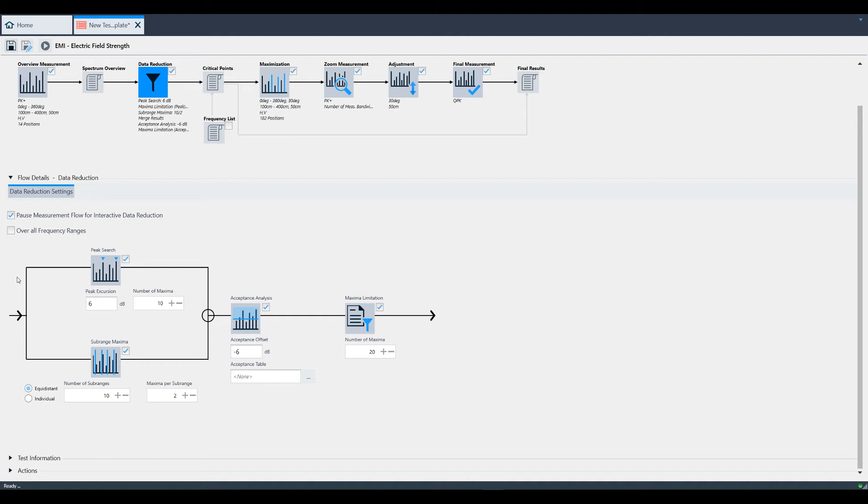In the block diagram, you see a block called peak search. This function, when enabled, will perform a peak excursion across the active frequency range to determine the number of peaks you define under number of maxima that are more than x dB down, where x is what you define in the peak excursion text box. In this example, x is 6 dB.